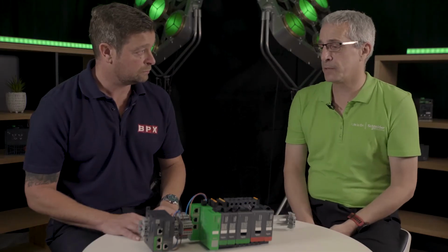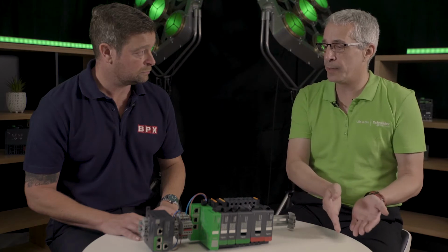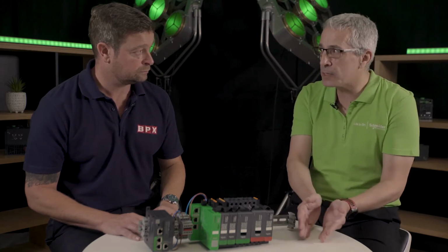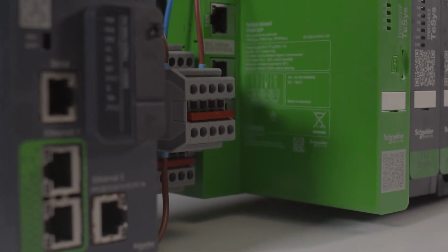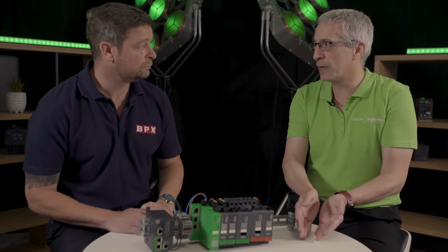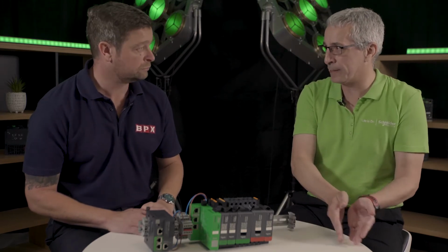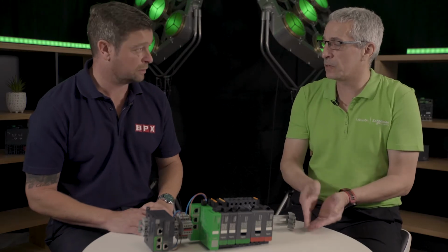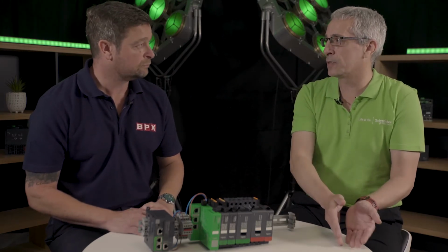That configuration software, something called SoMove, can also be implemented within the actual PLC software. So it can be a sub-program that is built into the PLC program. And then within that PLC program, you have a whole series of function blocks which replicate the avatars. So imagine from the first design stage, you've got a pump avatar, you use the online tool to create your bill of materials, you then import the configuration file that the online tool has created into SoMove to configure the TeSys Island, you then pick an associated avatar from the PLC software to then design and program and do the control.